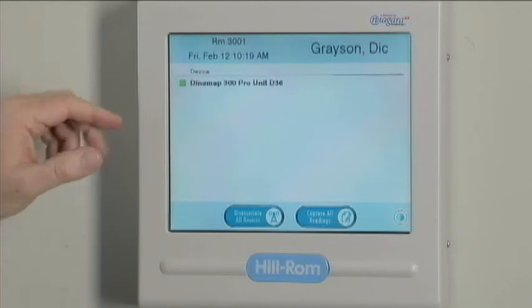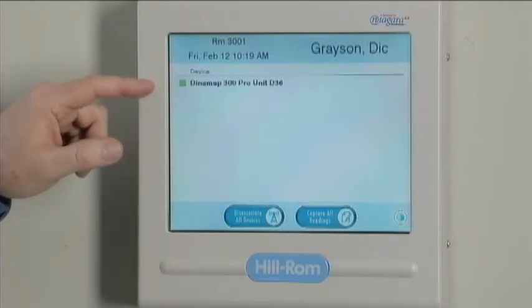So it just routinely now is collecting, and the data is being archived here in the hub. It's being routed from the hub up to the hub supervisor, and it's sending it to the hospital's EMR system for recording, and the nurse did not have to do any of those steps, didn't have to come to the room and chart the data, didn't have to take it back out to a workstation and enter it in. The data is just automatically being collected and routed back to the EMR system, which is the primary objective of the solution. And all of this functionality, all the work at the hub, our other components in the other spaces, the hub supervisor, the biomed configuration station, the MDA, they're all based on the Niagara AX framework and the capabilities that it has.